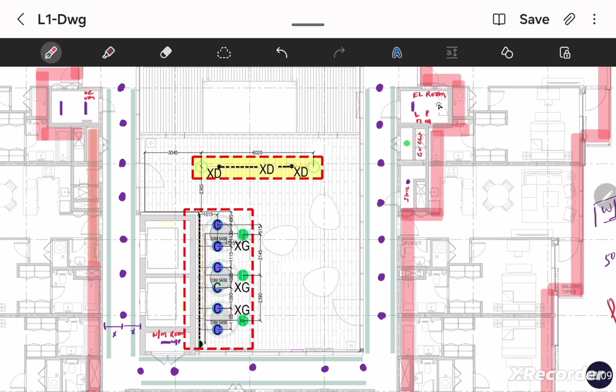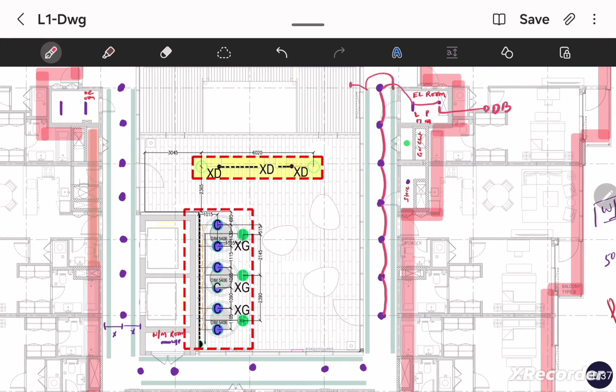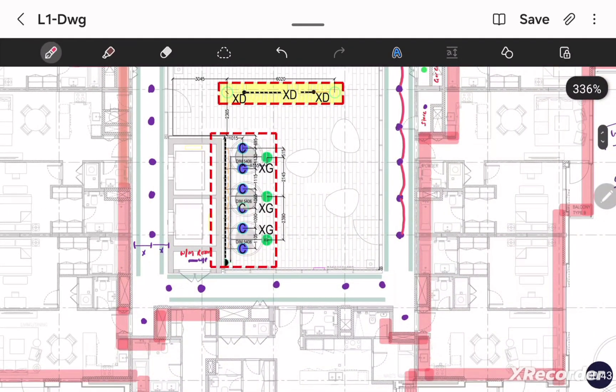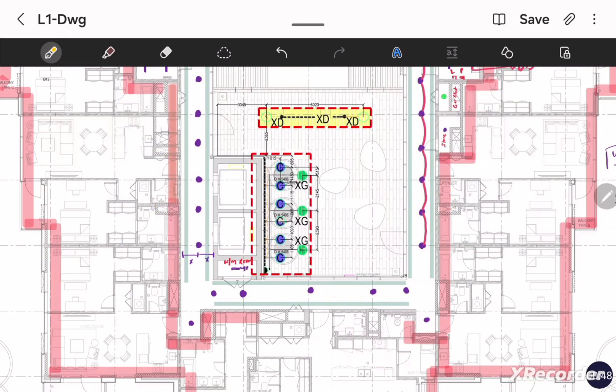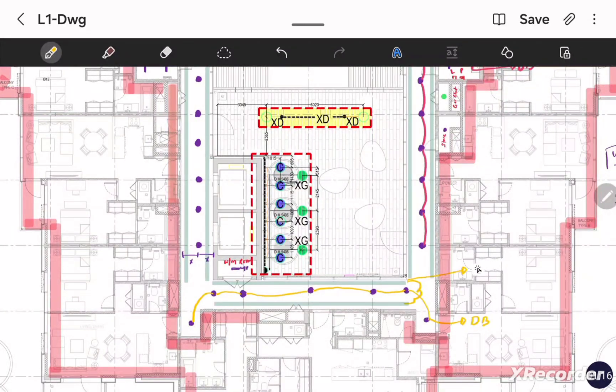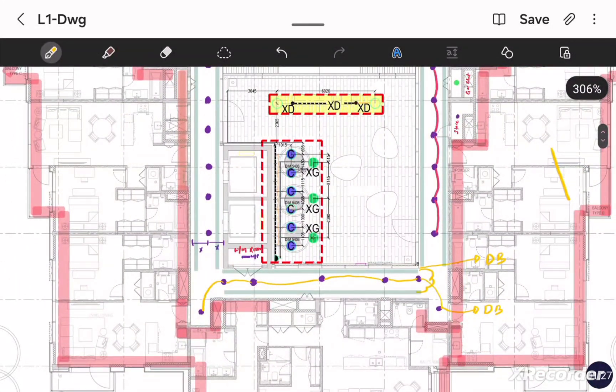Starting the circuit formation: the first light will go directly to the DB, and subsequent lights will be looped together — this light looped to this, to this, to this, to this, to this, to this, to this — completing one circuit. We give another circuit to the hidden light going to the DB. I assigned the R phase for this side corridor light. The opposite side corridor is given to another circuit — the Y circuit — looping those lights together.